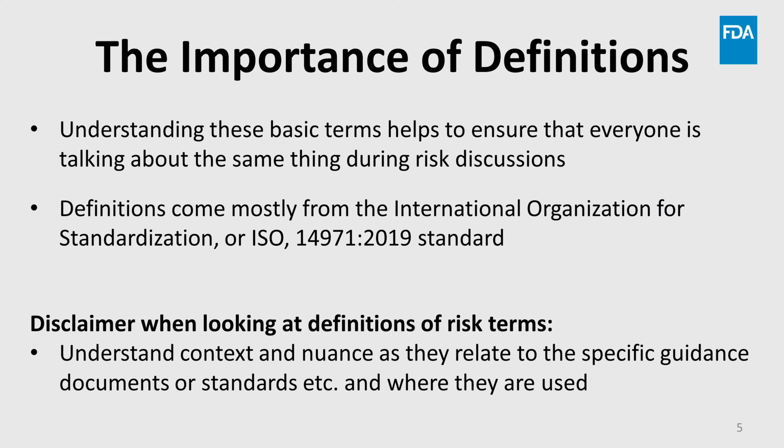To begin, we'll look at some important definitions. Understanding these basic terms becomes important as it will help to ensure that everyone is talking about the same thing during risk discussions. These definitions come mostly from the 2019 International Organization for Standardization, or ISO 14971 standard, medical devices, applications of risk management to medical devices. Please note that risk and risk-related terms are used by FDA. They are specifically used in several different FDA guidance documents that were written at different times and with different intents.